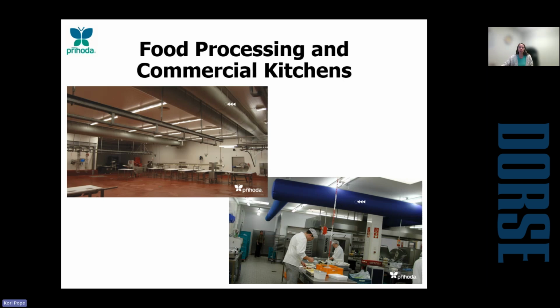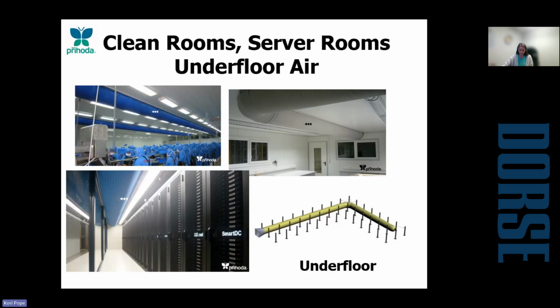condition those spaces. And what we're also seeing quite frequently with these applications is that they'll order 2 or 3 sets of fabric duct at a time. So that when one is down for laundering, they can go ahead and put up that other set, and there's virtually no downtime in the system. It's also great for any type of clean rooms, server rooms, or underfloor applications. Because of the endless fiber weaving and the ability to provide that soft and laminar airflow, fabric really is a no-brainer for these applications. So rather than having a ceiling full of HEPA diffusers, you can just have one HEPA filter at the air handler, and then we can distribute the air for the rest of the way.